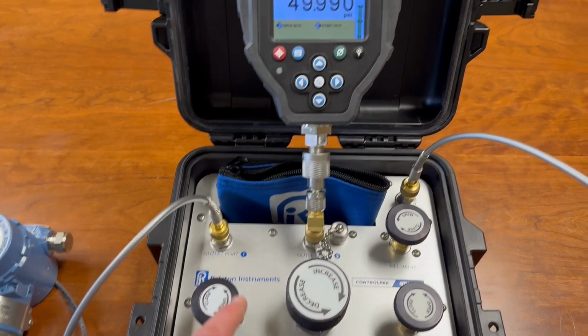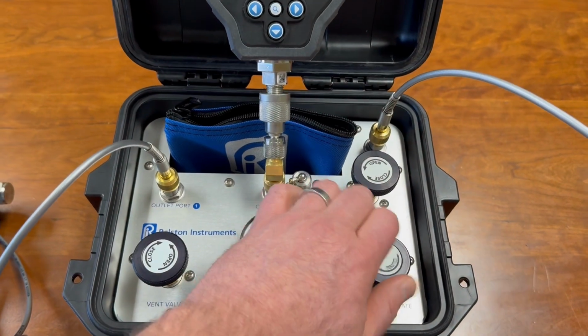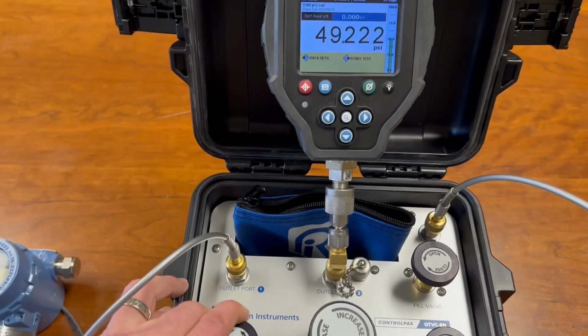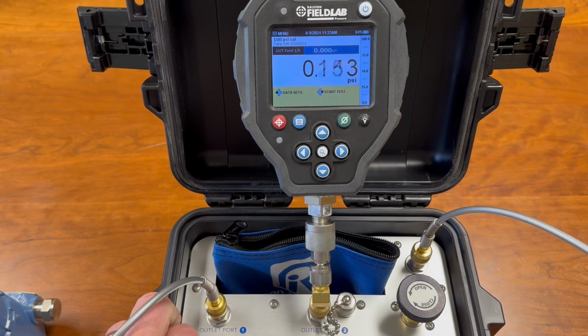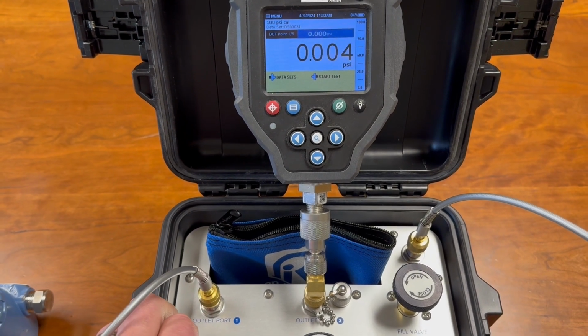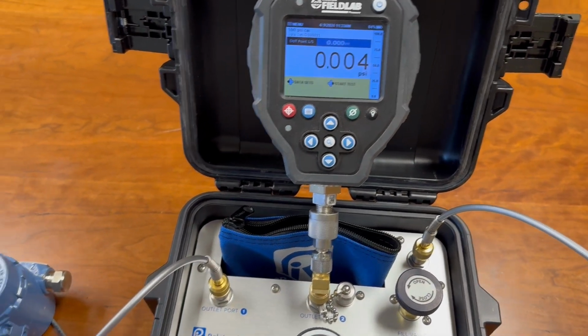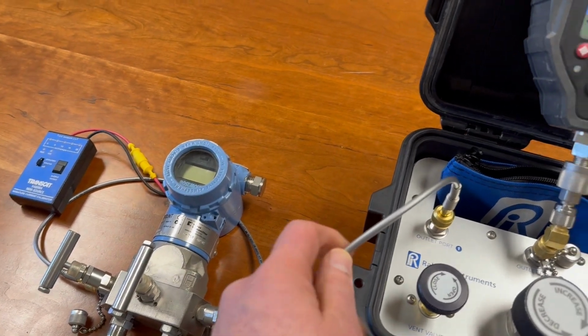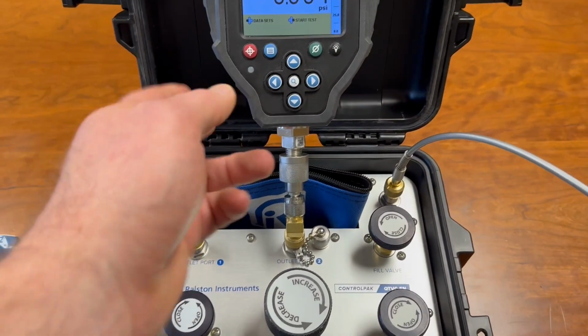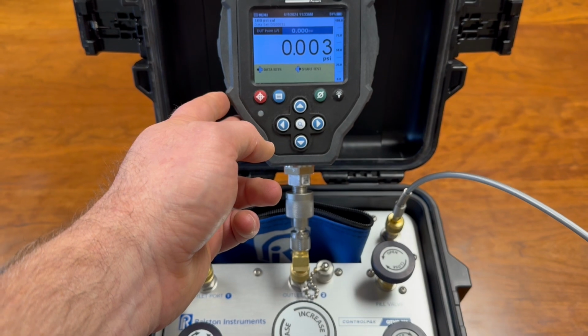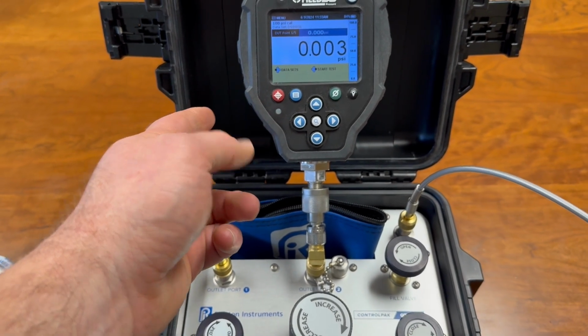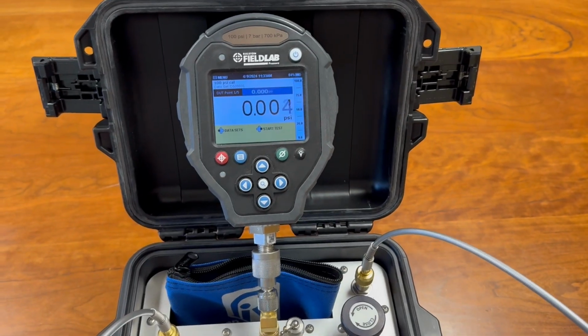And then when you're finished, you would simply open the equalize, vent the pressure off, and it will go back to 0. When all this is finished, you can disconnect your hoses, put them back in the bag, disconnect your pressure reference, and you're all ready to go. Good job, Griff, great demo. As you guys see, it's all set up.